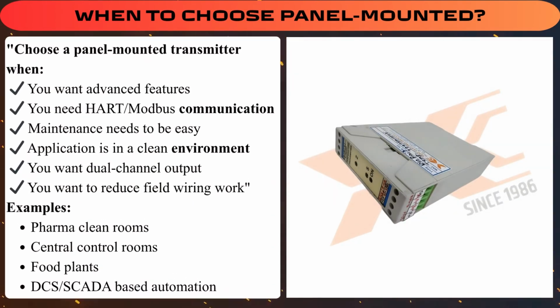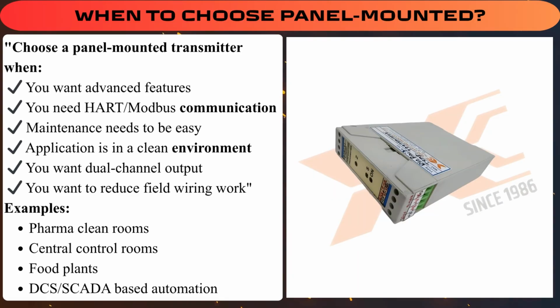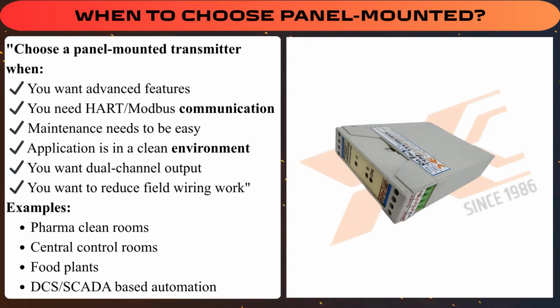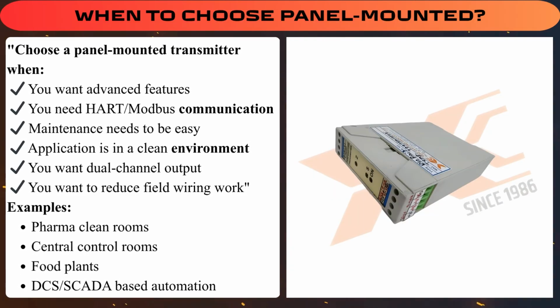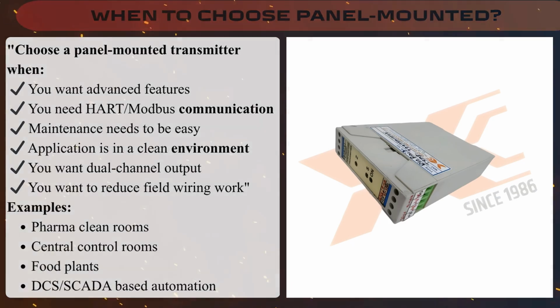When to choose panel mounted? Choose a panel mounted transmitter when you want advanced features, you need HART, Modbus communication, maintenance needs to be easy, application is in a clean environment, you want dual channel output, or you want to reduce field wiring work. Examples: pharma clean rooms, central control rooms, food plants, DCS, SCADA-based automation.